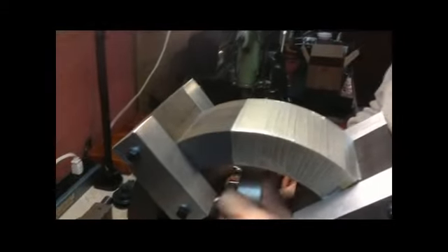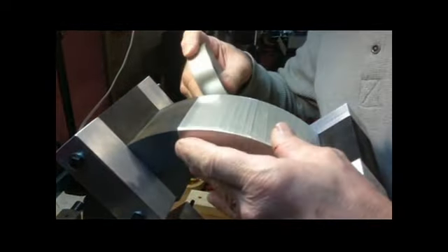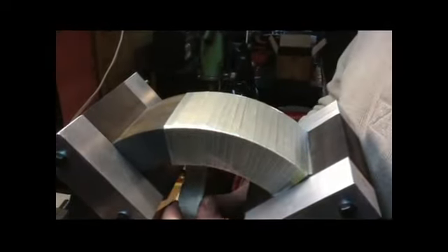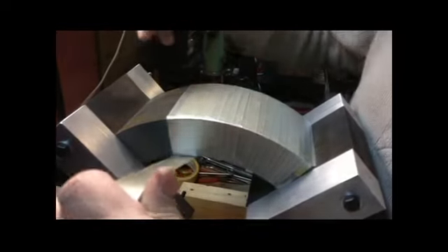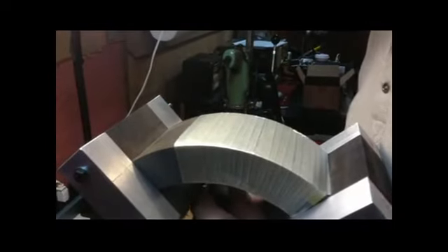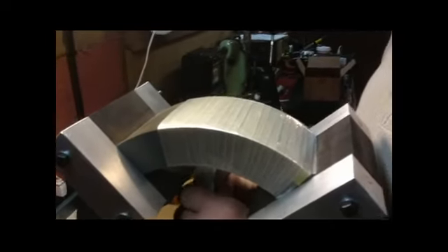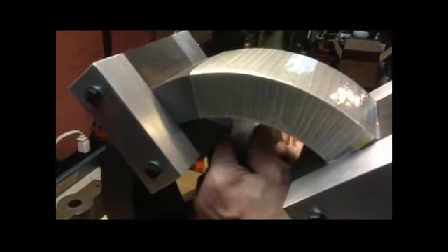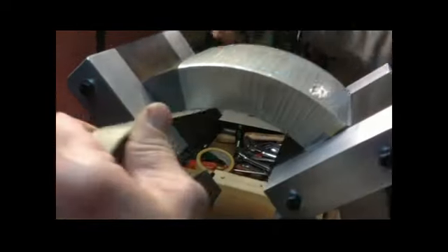This tape has been tested to see how much voltage it will withstand before it punches through and arcs. It will withstand 1500 volts per mil, and this is a 6 mil tape. The target is to make sure we can hold off 25,000 volts. So 1500 times what gives you 25,000.